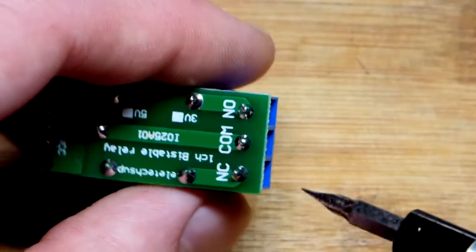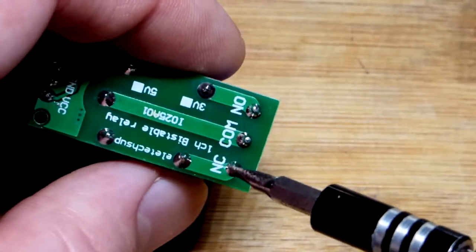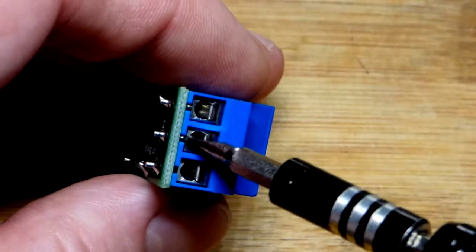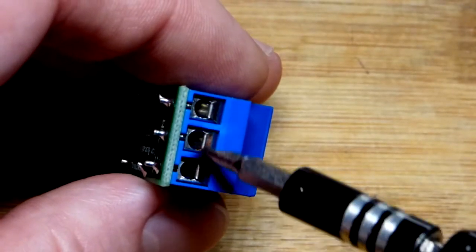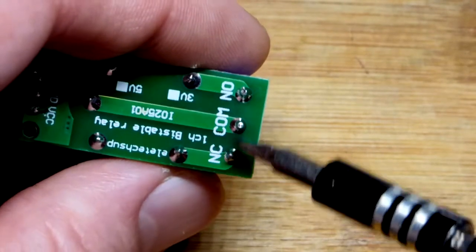We have a normally closed pin, and first off there's common. This is always connected to the mechanical switch part of it. Sometimes it's connected to that pin, sometimes to that pin with direct connection. Normally closed means when the coil is not energized, it's connected right there, those two pins directly.